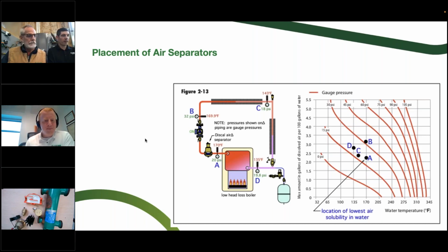Okay, so let's look at the last category of air that we talked about with air separation, which is the gases dissolved within the water, or the glycol. So how do we catch those? It's based on our air separator placement. We want it in the hottest temperature with the lowest solubility. So in this simplified example of a piping loop here, this is the hottest temperature coming out of the cast iron boiler at 170 Fahrenheit at 20 PSI. So the pressure is low.